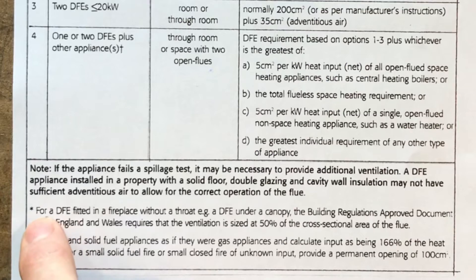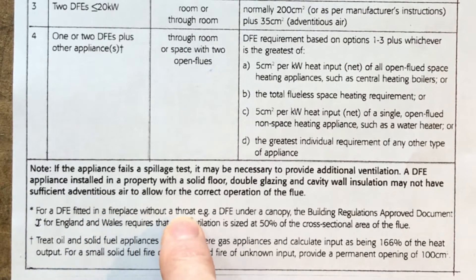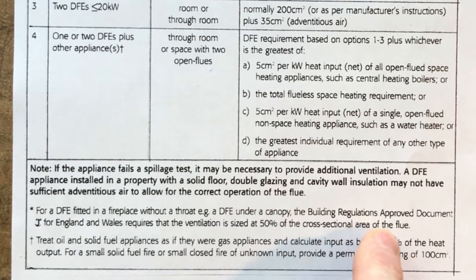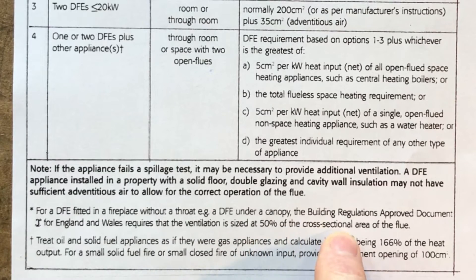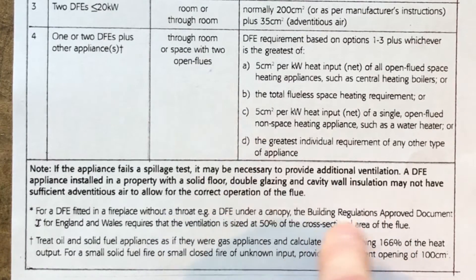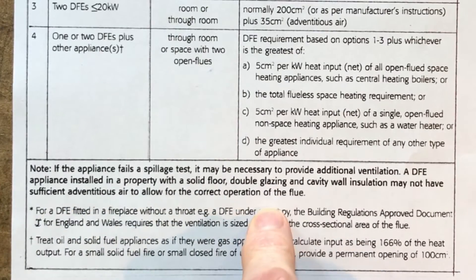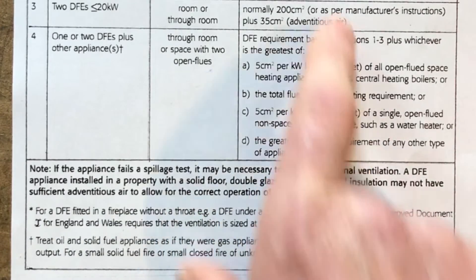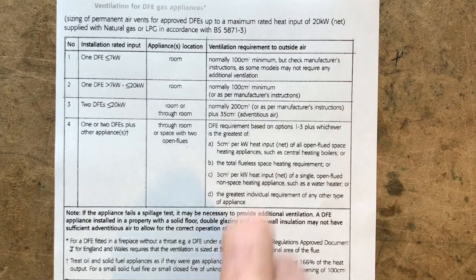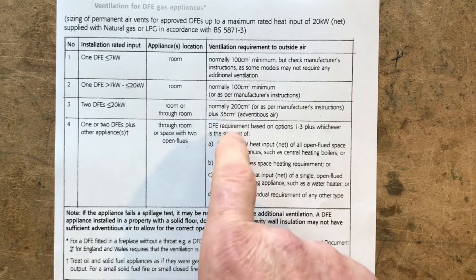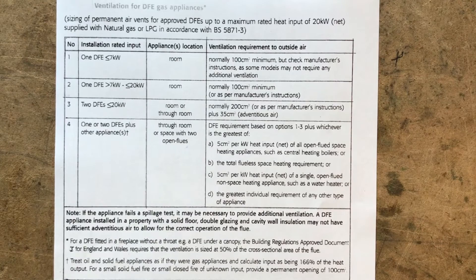The chart also notes at the bottom that for a DFE fire fitted in a fireplace without a throat — for example a DFE fire under a canopy — Building Regulations Approved Document J for England and Wales requires ventilation to be sized as 50% of the cross-sectional area of the flue. Most of the time these DFE fires are under 20 kilowatts. I'll leave this chart up for a few seconds so you can read it or you can pause it.